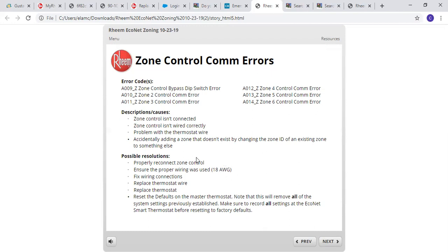Some possible resolutions: properly reconnect your zone control. Ensure the proper wiring was used, which is 18 gauge. Fix wiring connections. Replace thermostat wire. Replace thermostat. Reset the defaults on the master stat. Note if you do reset to defaults, this will remove all of the system settings previously established. So if you do reset to factory defaults, you have to go all the way through your duct test and your linearization test as well.